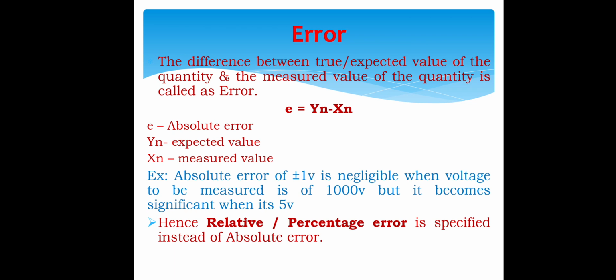Next, error. The difference between the true or expected value and the measured value of the quantity is called error. The formula is e equals yn minus xn, where e is the absolute error, yn is the expected value, and xn is the measured value. The difference is the error. An absolute error of plus or minus 1 volt is negligible when the voltage being measured is 1000 volts, but it becomes significant when it is 5 volts.